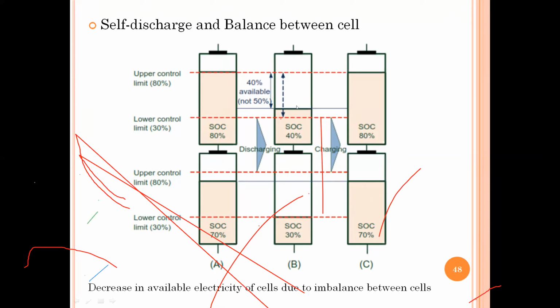When you go for the charging, this upper battery, it is reaching to its upper limit earlier. And this lower battery, it is still remaining with 10% of the SOC. It is not going to reach to the 80% of SOC. It is remaining at the 70% of the SOC. So there is an imbalance. Due to that, there is a less utility of the capacity of the battery.